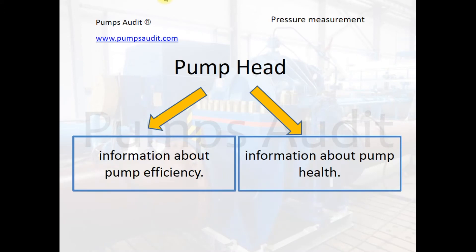As I said at the beginning, pump head is a very informative value. If we have the value of the pump head and the curve of the pump, we can define the position of the operating point on the QH curve. We can define flow, power, and NPSH. If we have track records of pump head values, we can also evaluate the condition of the pump and its deterioration over time.